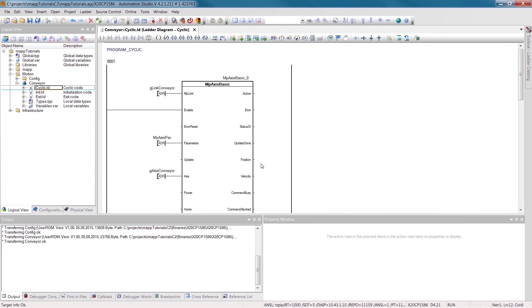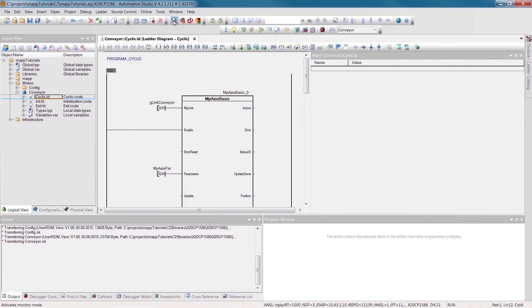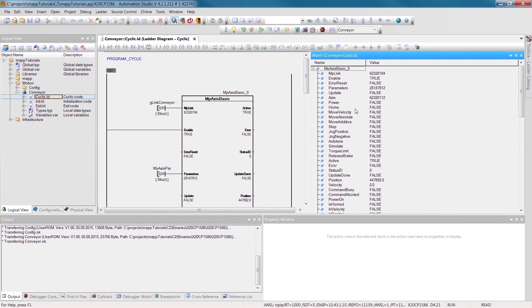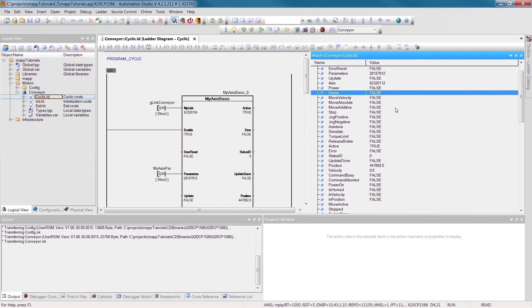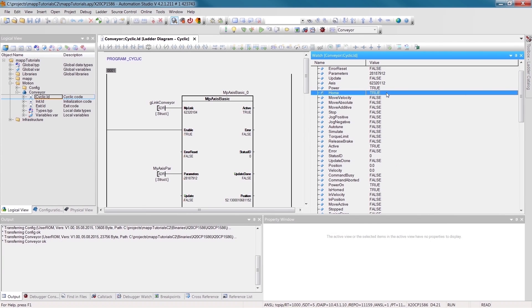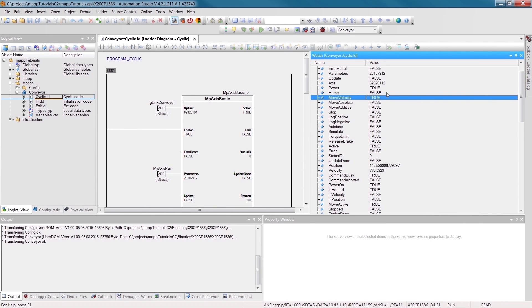Now we want to start the axis. We'll turn on monitor mode so that we can manually set commands. First, we'll switch on the controller. Then we'll home the axis. The outputs of the MpAxisBasic component show us whether these actions are successful. Using the MoveVelocity command, we can start a movement with the parameter settings we made. And look at that — the axis is turning.